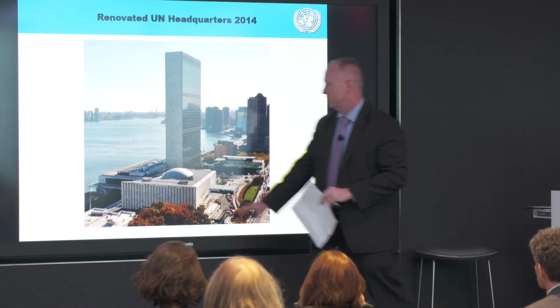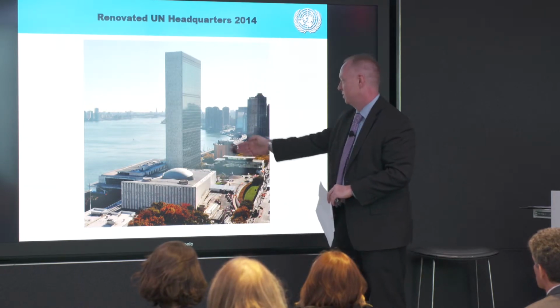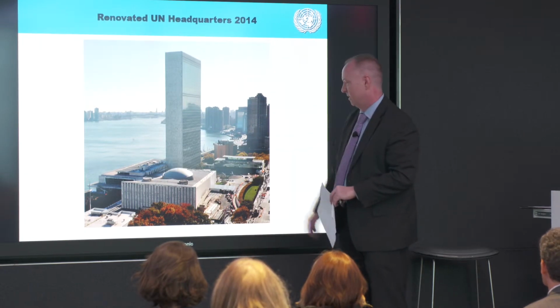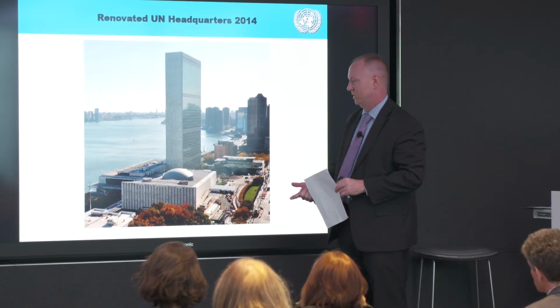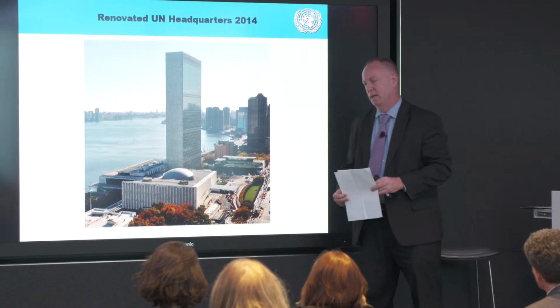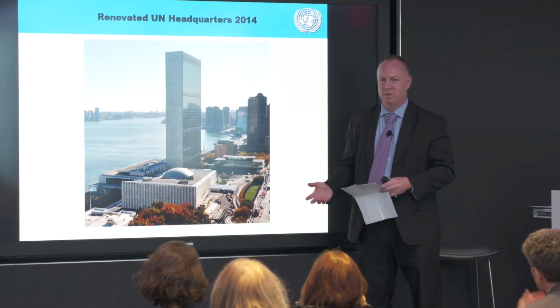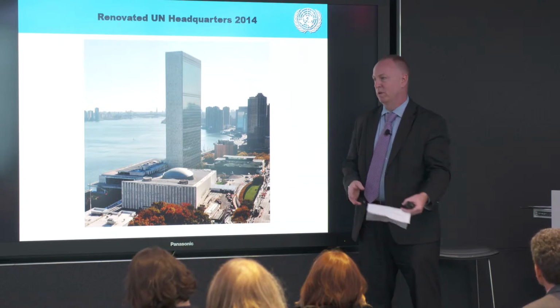We ended up with basically our sexy chiller plant, which is located right at the bottom of this. 42nd Street is here, 48th is here, FDR runs underneath the United Nations, and this is First Avenue. So we have Con Ed steam, and Con Ed electricity enters the facility. It used to be an all-steam chiller plant, and we ended up going with a hybrid plant now for redundancy in fuel source. So if we ever were to lose Con Ed steam, we could run on electricity.